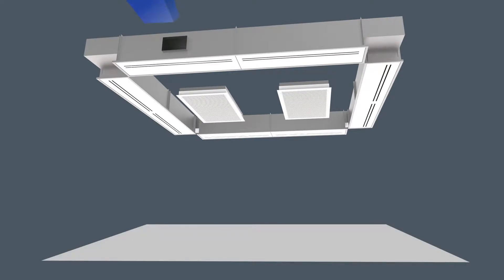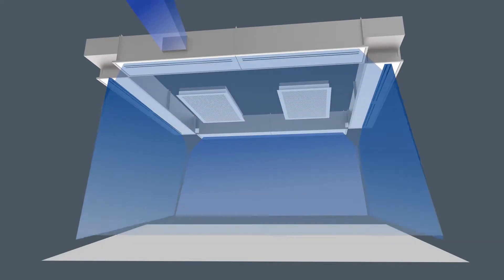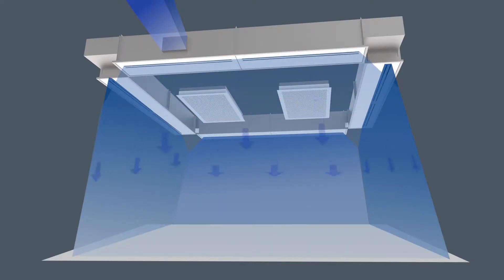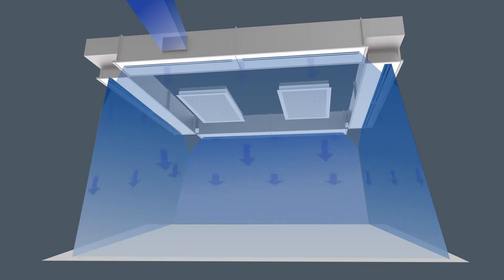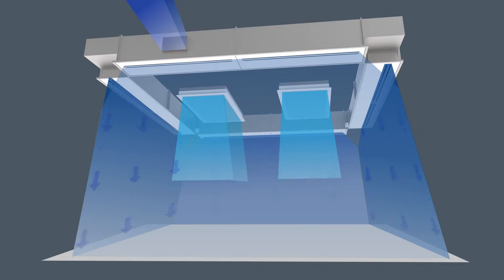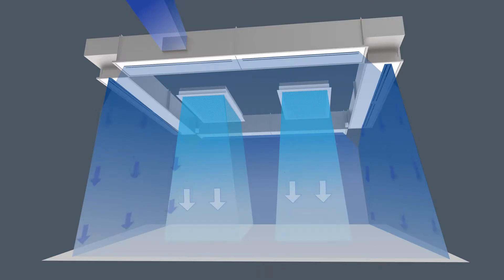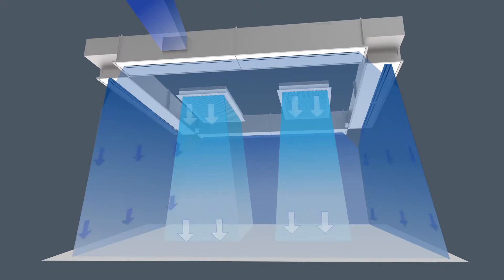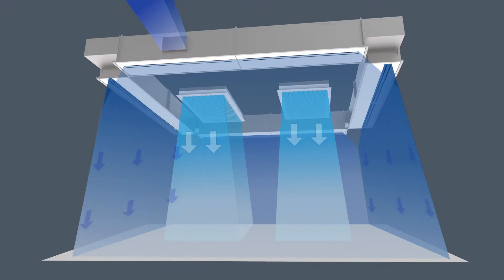The superior solution is the Metal Air Paraflow System. Paraflow is an air curtain system comprised of perimeter slot diffusers that create a wall of outward angled air, combined with laminar flow diffusers centered above the operating table. The air barrier created at the operating table encloses the patient and the surgical staff, effectively separating them from the rest of the OR, while pushing contaminants to the floor, preventing migration onto the patient.